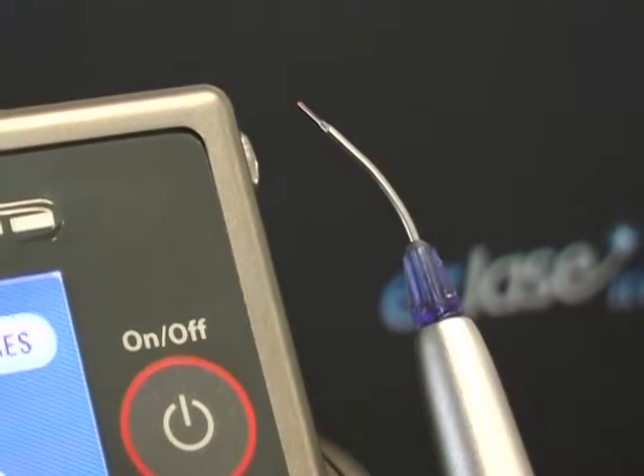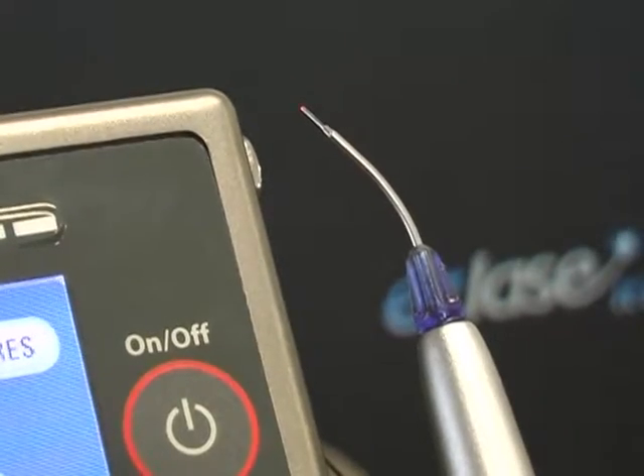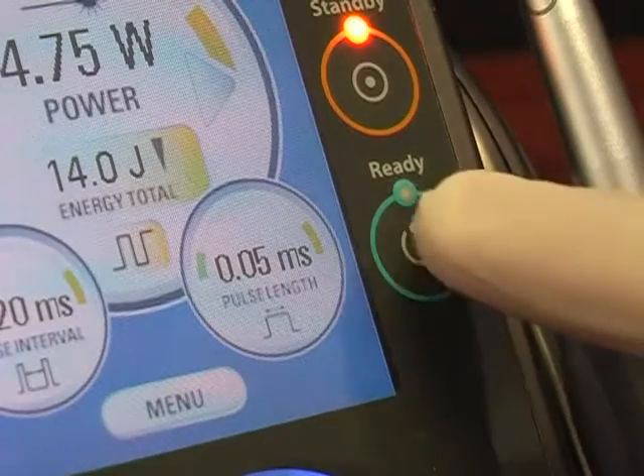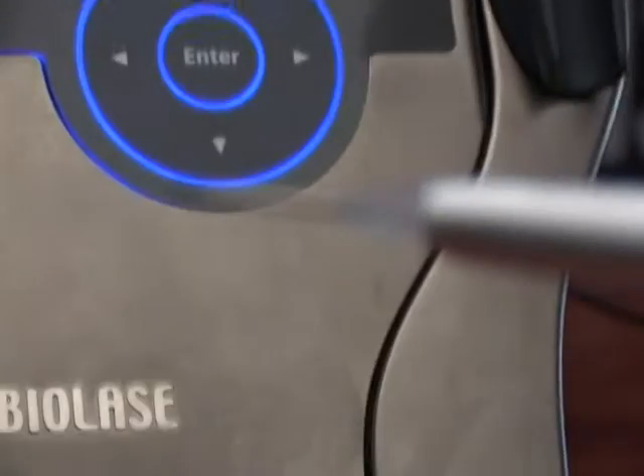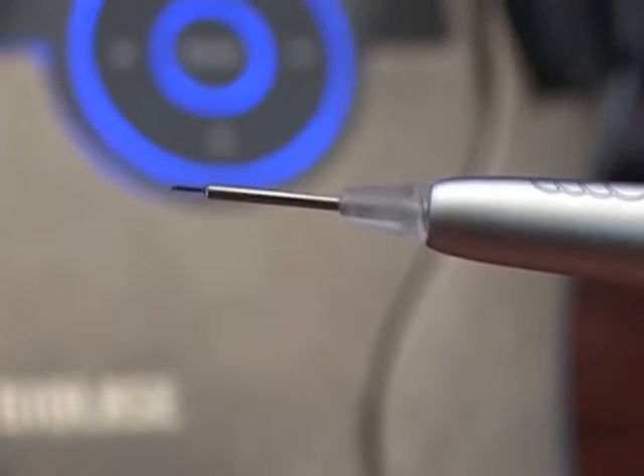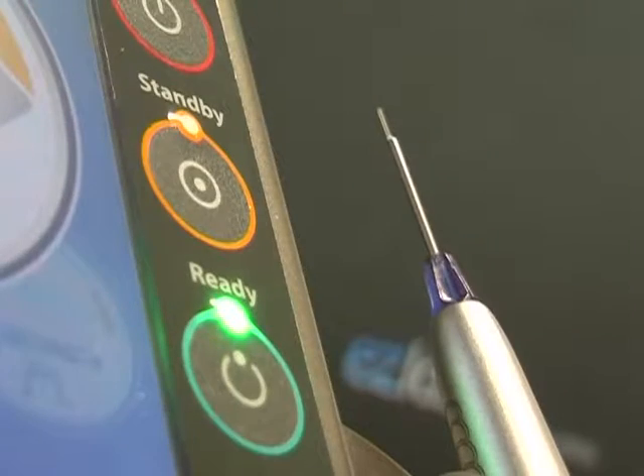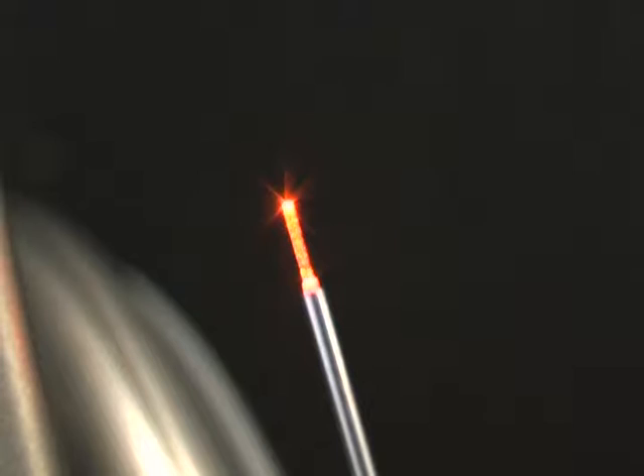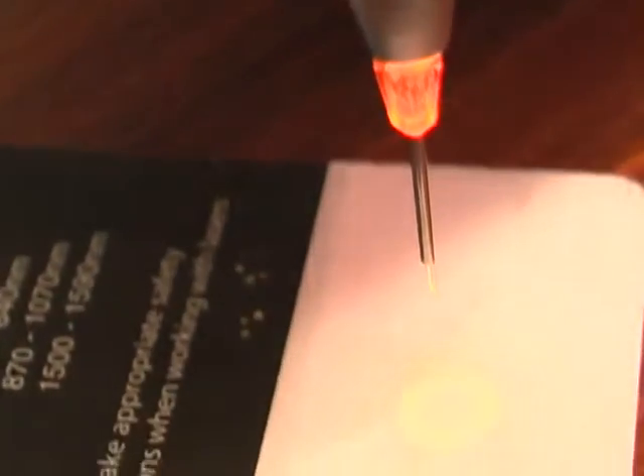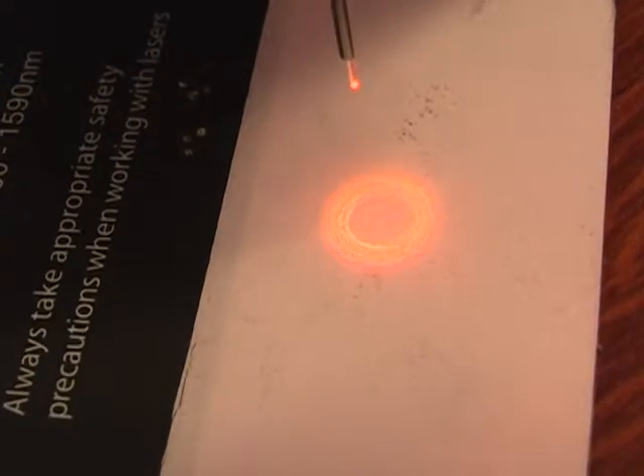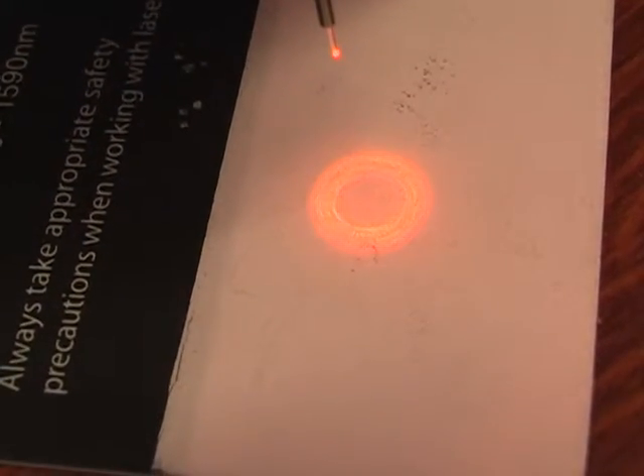The aiming beam will activate when you put the system into ready mode. Because the 940nm laser light, as well as the 810nm, used for treatment is invisible to the human eye, a red, visible aiming beam is provided so you can visualize the area of the tissue that has been exposed to the laser energy. The red aiming beam appears as a circular annulus or donut pattern. The treatment beam will be located inside the central disc where there is no red light.